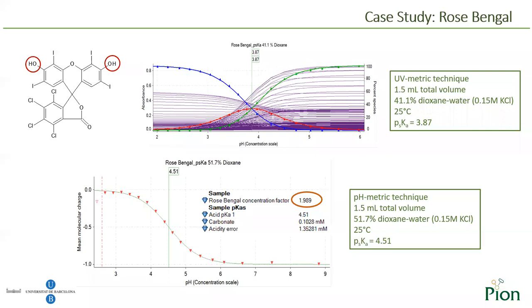The spectrometric and potentiometric techniques used by the D3 are complementary to one another, and the same story has to be explained by both. This is the reason that in analytical service, we always use both to confirm results, and we highly recommend using them together for the determination of any pKa.